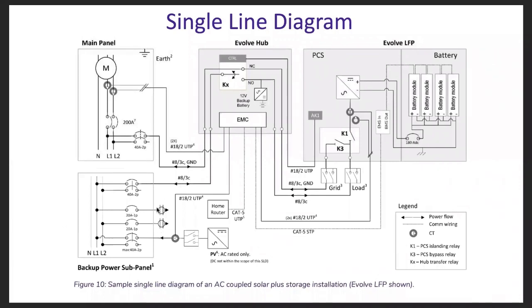I won't get into too much detail here, but this is basically just a single line diagram version of the conduit plan or block diagram that I showed earlier, where the main panel in this case is a 200 amp panel with the maxed out 40 amp backfeed breaker, the backup power sub panel, the PV being landed at that backup power sub panel, and the Evolve Hub. This shows the switching, basically the ATS functionality within the Evolve Hub, for when grid tied versus when in off-grid mode, or if the battery's offline or before it's commissioned and turned on. This will route that same backup power sub panel to the service panel. So a pretty good amount of flexibility, and pretty easy to install, pretty basic here.